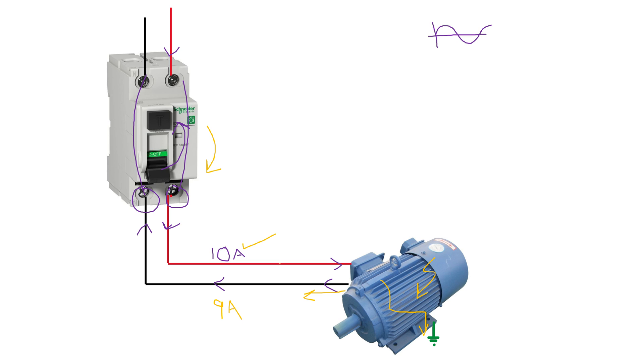If a fault occurred over here, we would also have an imbalance between the current coming in and the current going out. And if a fault occurred over here on the neutral — if the neutral for some reason went to ground — we would also have a trip of the earth leakage. So the purpose of the RCD is to measure the difference in current coming in and current going out. When there's a difference of more than 30 milliamps in most cases, the RCD must operate.